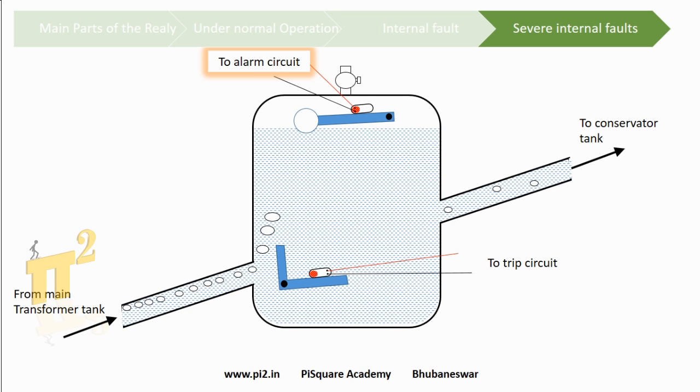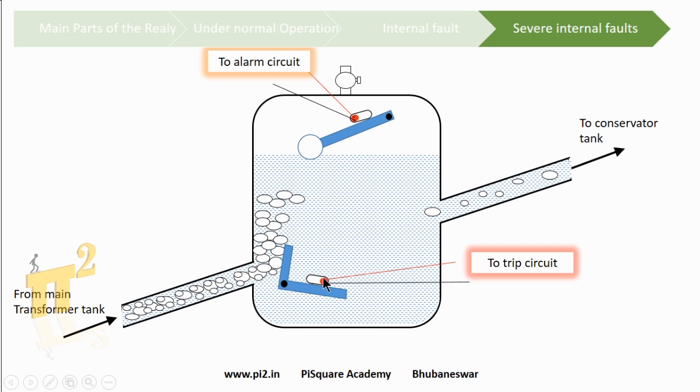If there is a severe fault, there is a heavy rush of gas which hits the baffle plate. This causes the mercury switch to engage the trip circuit, which will then activate the circuit breaker.